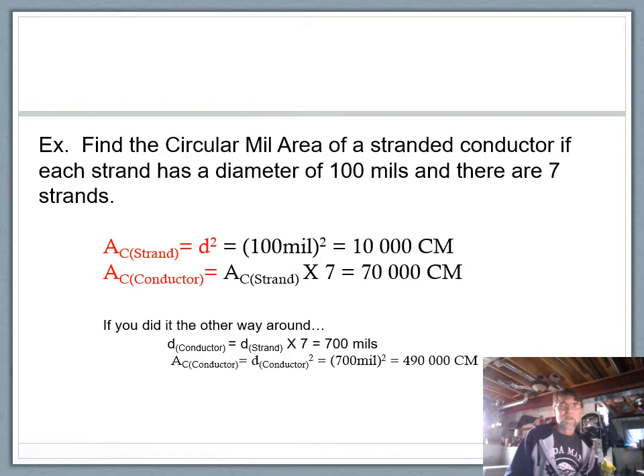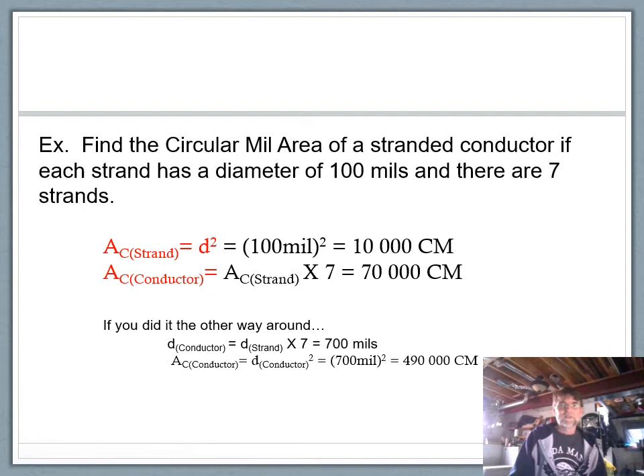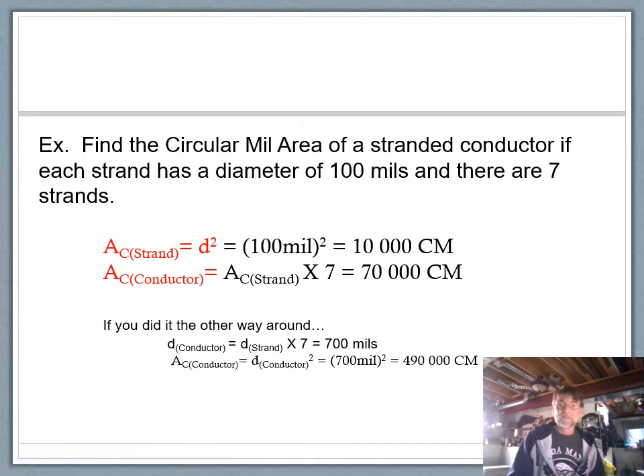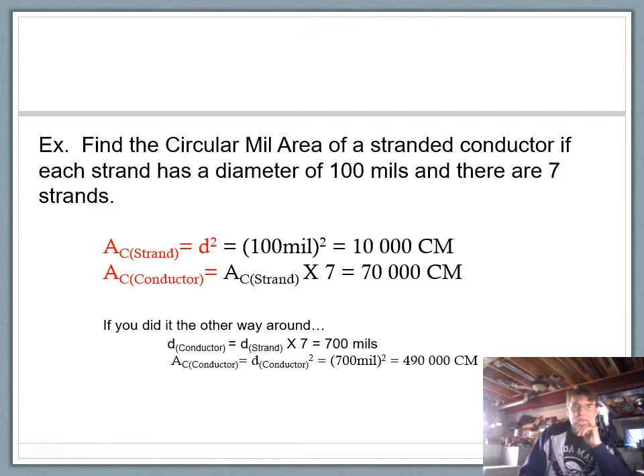Here's the example: find the circular mil area of a stranded conductor if each strand has a diameter of 100 mils and there are seven strands. The circular mil area per strand is simply d squared: 100 mils squared gives you 10,000 circular mils. Then multiply by the seven strands, giving 70,000 circular mils as your final answer.